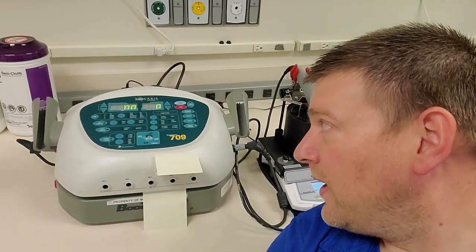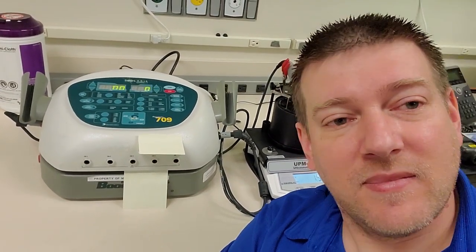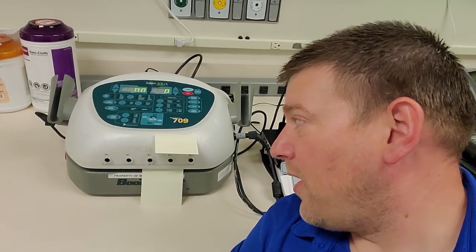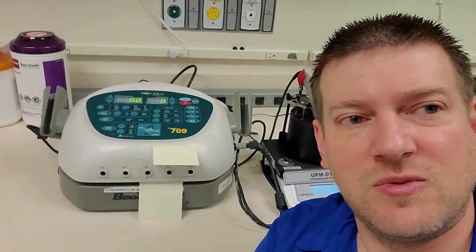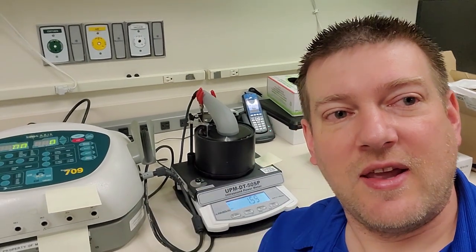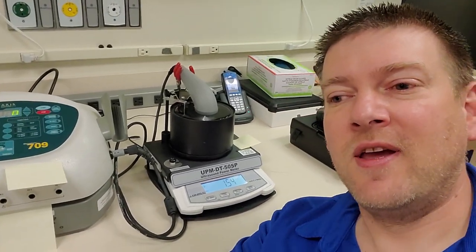So guys, that is ultrasonic therapy. It's kind of a simple system - it just heats up tissue to allow more blood circulation which speeds up the healing process in deep tissue. But it's an important piece to all physical therapy areas. And although they don't use a lot of these other features, we still have to test them when we do a PM. But the main thing here is your ultrasound head. And be very, very careful while you're doing your measurements and write all your settings down, because you might erase your settings like I did. So guys, that is ultrasonic therapy. Thanks for watching.